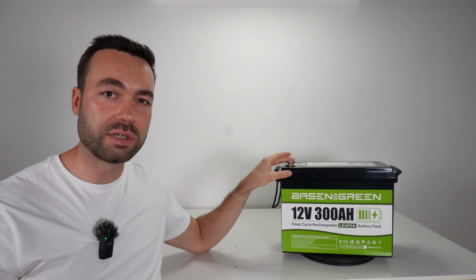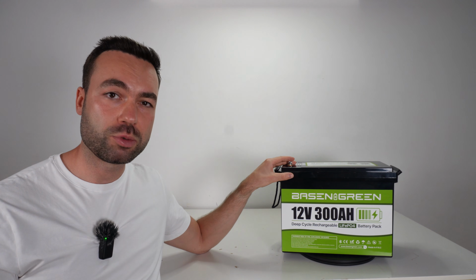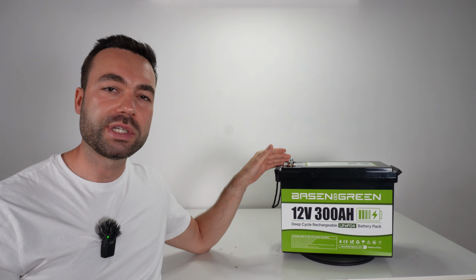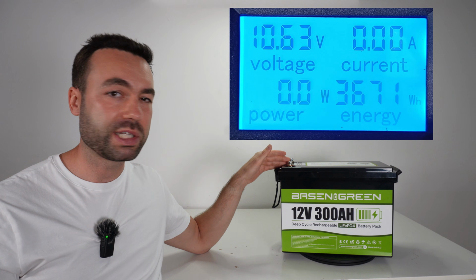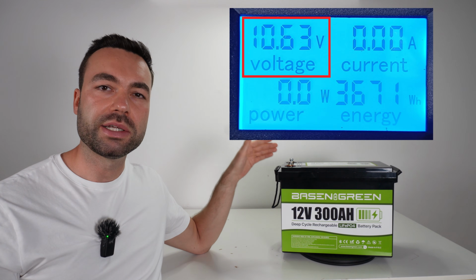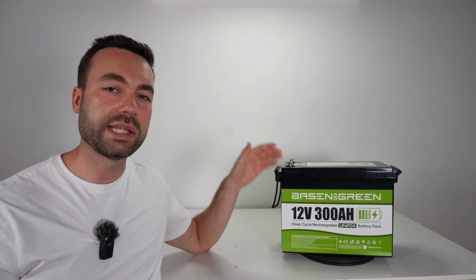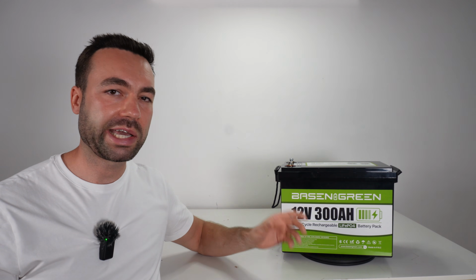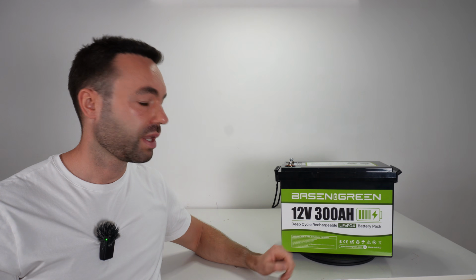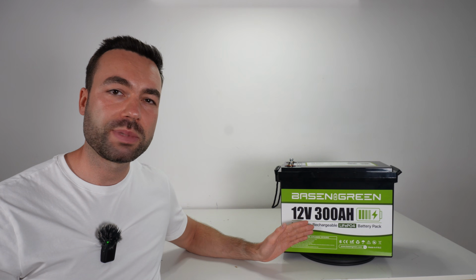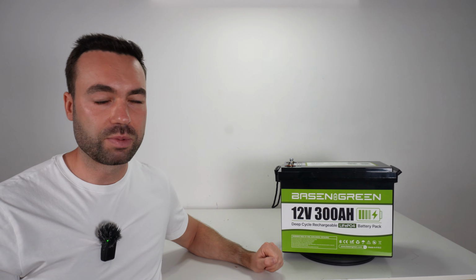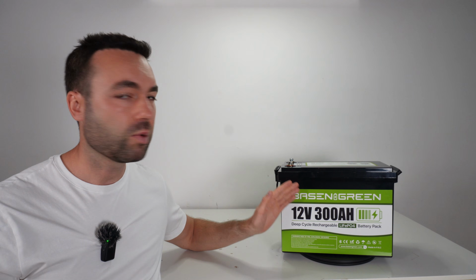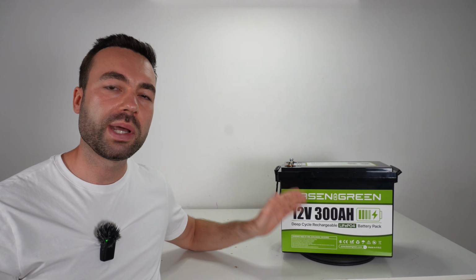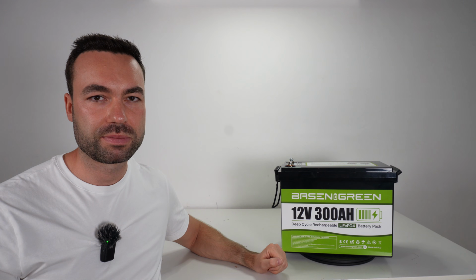I usually test the batteries at a 0.2 C rate, and whenever the inverter starts to beep, which is at 11 volts, the test is finished. That's how I perform all my capacity tests. The manufacturer even told me my way of testing is wrong. So we will see what cells they're using when I do the teardown.